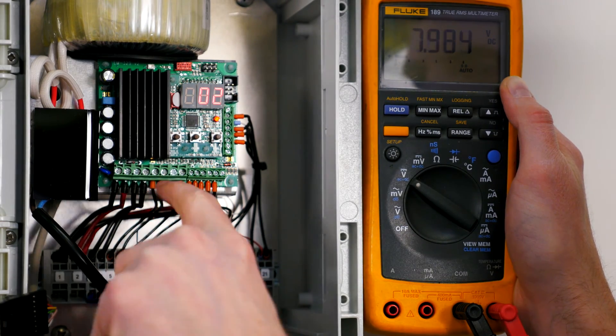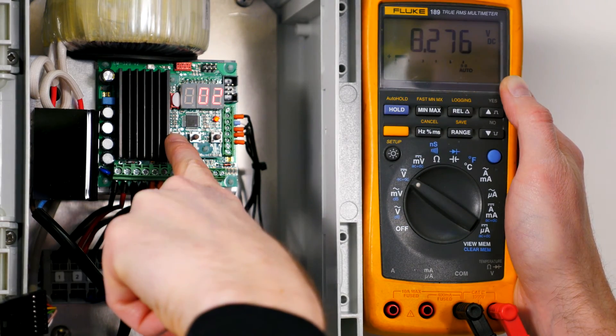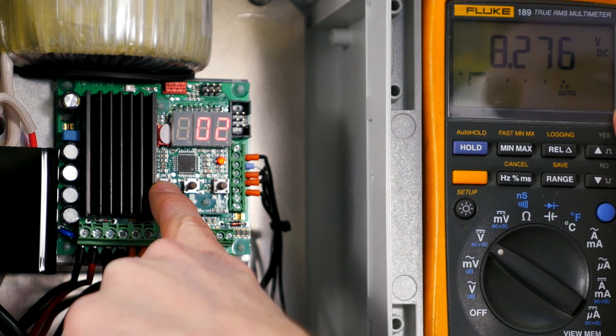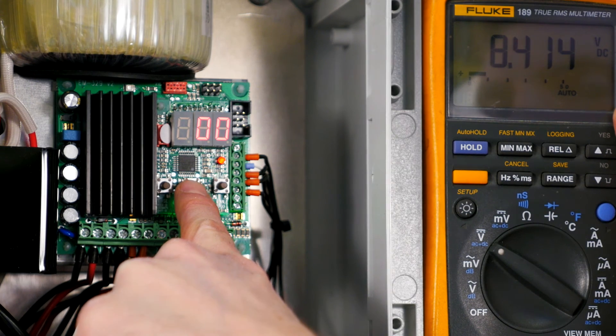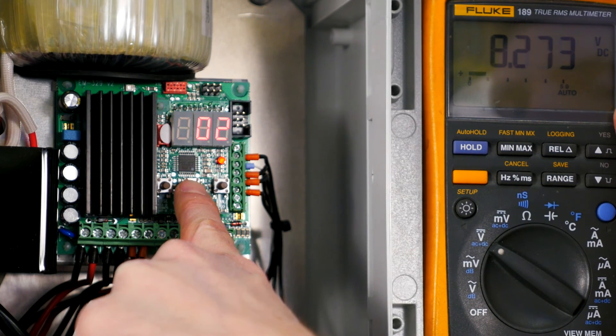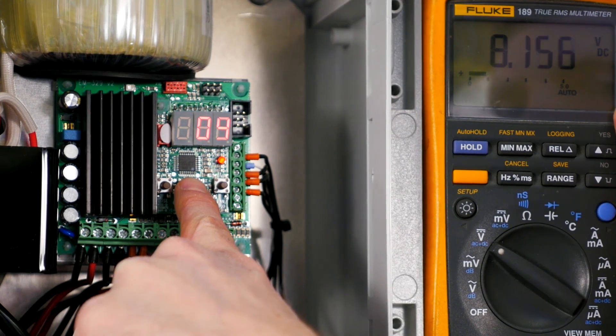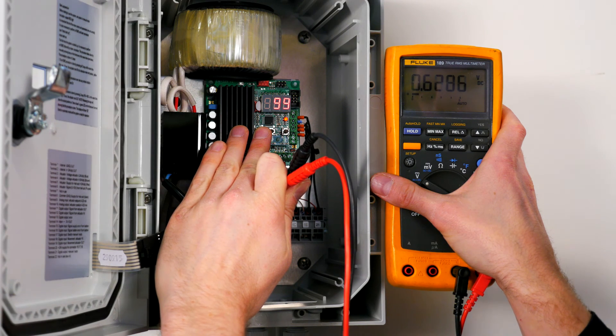Check if there are errors in the feedback by measuring whether there is a voltage between terminals 6 and 8, which vary during the reset procedure. When the actuator is retracted, the voltage must be 0 volts. Once this is your reference point, when the actuator runs outwards, the voltage must increase.